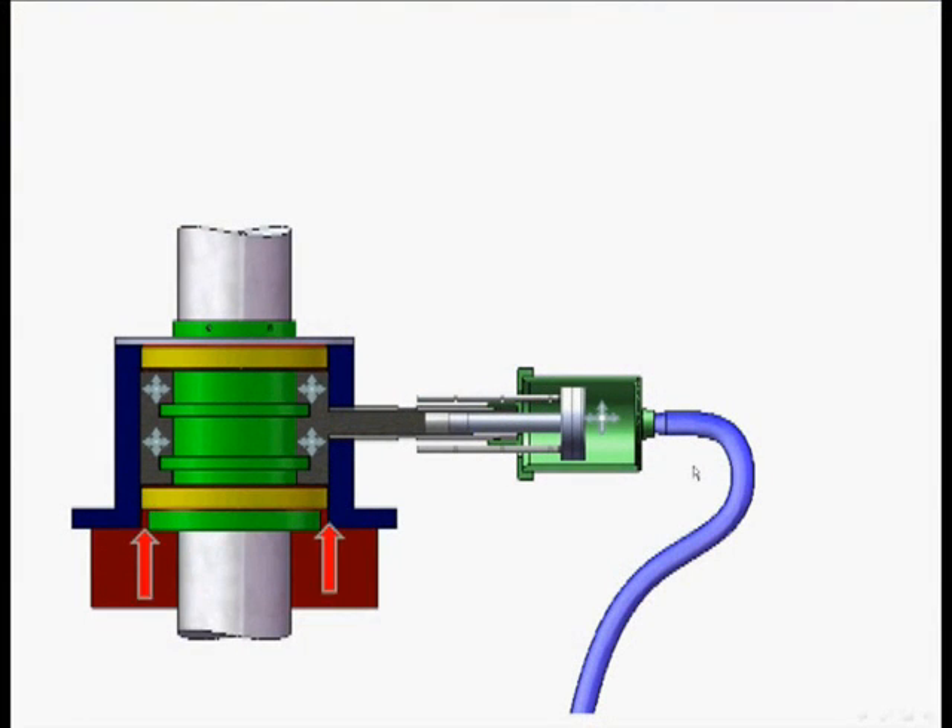The principle of MTZ technology is quite simple, and it is based on a sealant automatically injected into a specially designed stuffing box. Using a constant positive pressure inside the stuffing box creates a barrier to prevent leakage from a process even under extreme conditions. MTZ technology is a simple, flexible, dynamic plug-and-play seal replacement solution for any seal in the market.